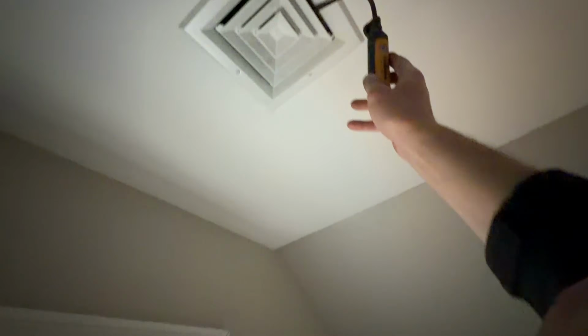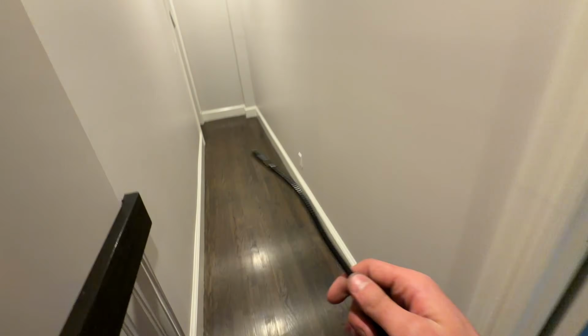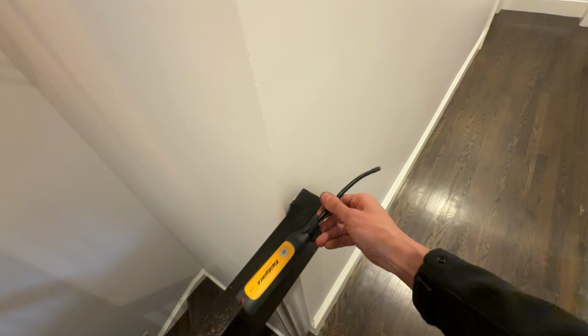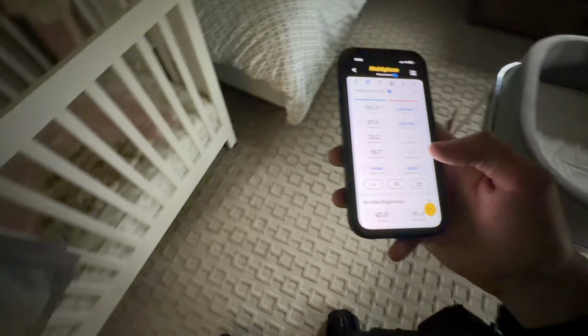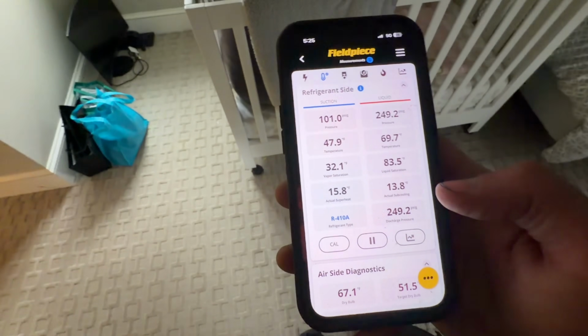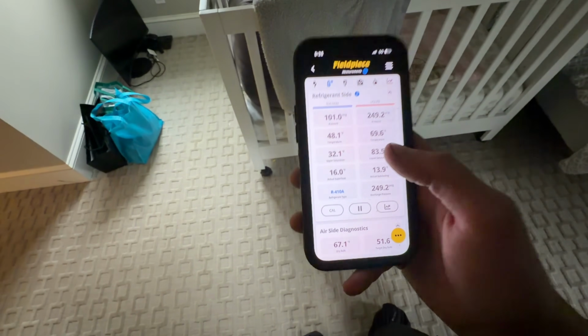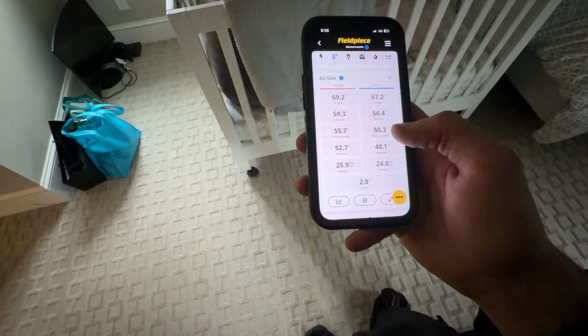Okay, here's our thermostat. So we got 73 degrees inside. This is my supply psychrometer, which I'm gonna stick right there. Our return is right there. Just gonna put it right here. It's close enough. Now, we could take a look. My probes outside are connecting, even though they're all the way downstairs, which is another reason I like the Fieldpiece.